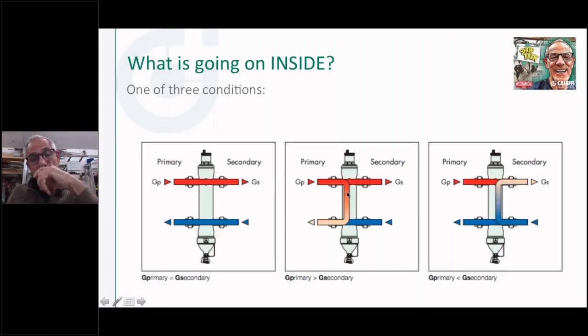Now, that's a reason that if you want to, we put a sensor well in here, but really if you want to put a sensor on that's going to modulate your boiler based on what's actually going out to your system, I'd like to see that sensor downstream about 6 inches, so I'm actually measuring the blended temperature. If I put that sensor in there, I'm going to measure the temperature right here, but that doesn't necessarily mean that's what's going to be going out to the distribution. So either put a well in there, or strap on a sensor and insulate it well, and use that to tell the boiler what's going out to your distribution, if you want to modulate your boiler temperature by what's actually going out to the load.